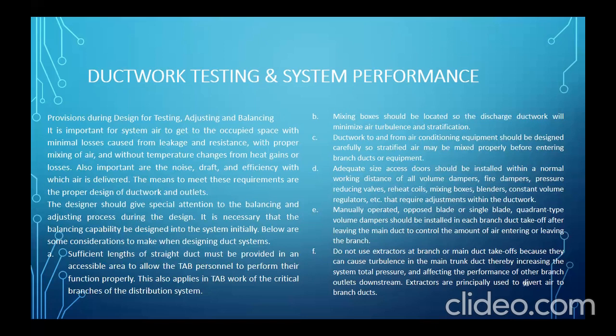Below are some considerations to make when designing a duct system. A. Sufficient length of straight duct must be provided in an accessible area to allow the TAB personnel to perform their function properly. This also applies to the critical branches of the distribution system. B. Mixing boxes should be located so the discharge ductwork will minimize air turbulence and stratification. C. Ductwork to and from air conditioning equipment should be designed carefully so stratified air may be mixed properly before entering branch ducts or equipment.